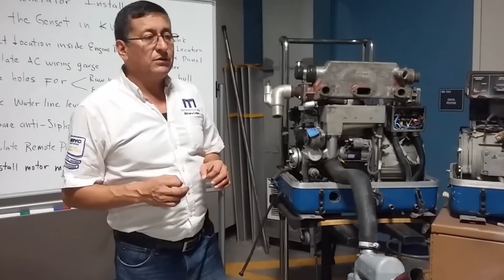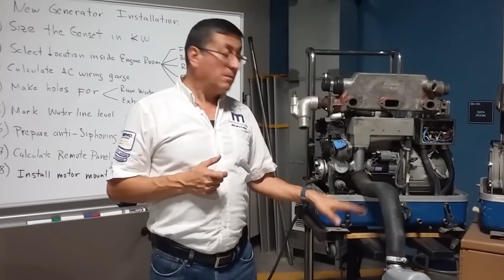I have a lot of experience with generators improperly installed that later have problems. The insurance company's first step is to verify where the muffler is located. If the muffler is not below the bottom of the generator, there's no warranty, no claim. Be careful with the installation of the muffler - it should be located below the level of the generator, minimum 2 inches.